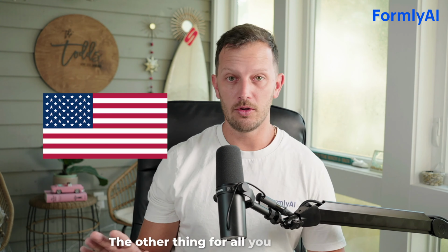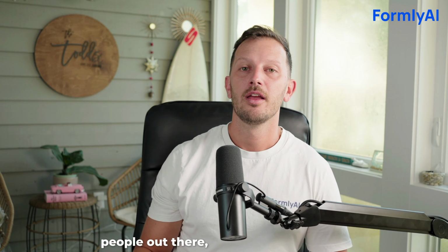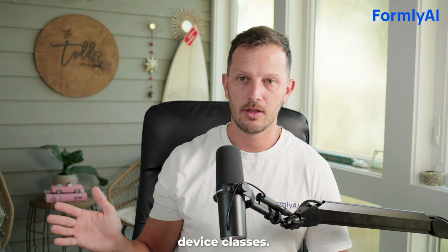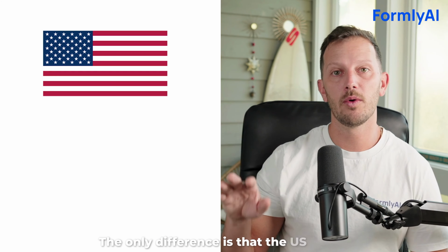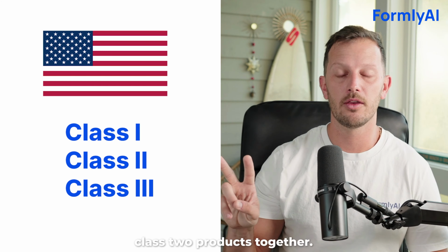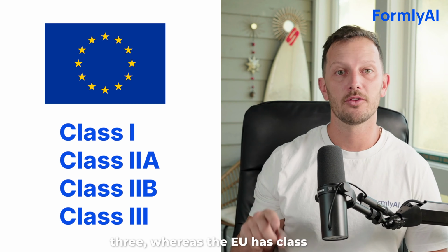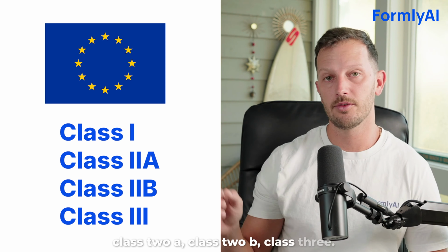The other thing for all you US-centric people out there, the US has a different set of device classes, but they're essentially the same idea as European device classes. The only difference is that the US lumps Class 2 products together. So they have Class 1, Class 2, Class 3, whereas the EU has Class 1, Class 2A, Class 2B, Class 3. Let's talk about what type of devices make up each class.